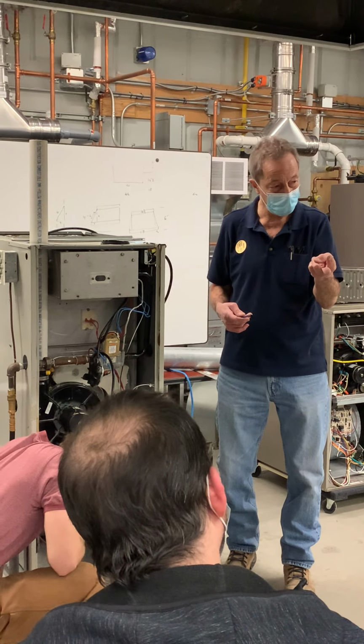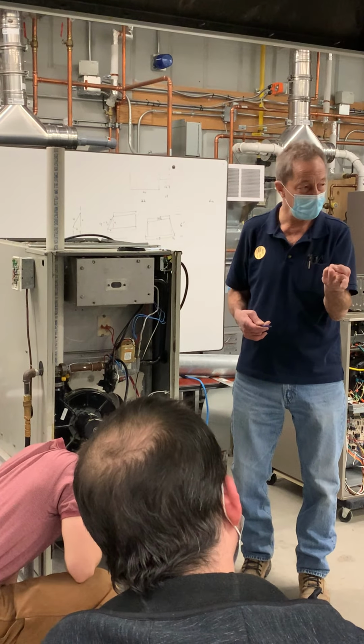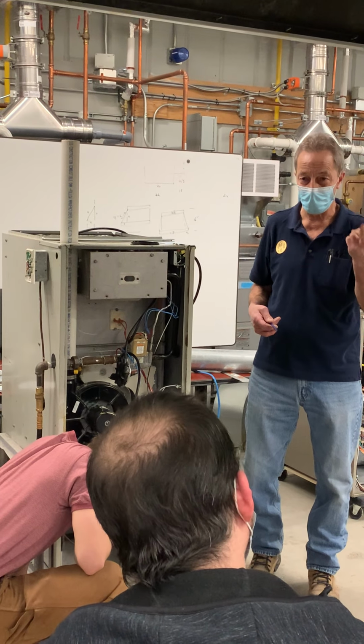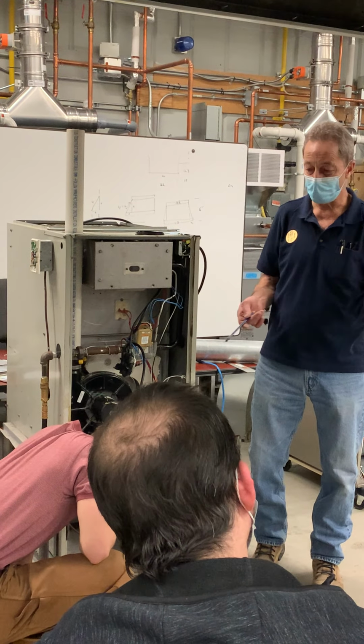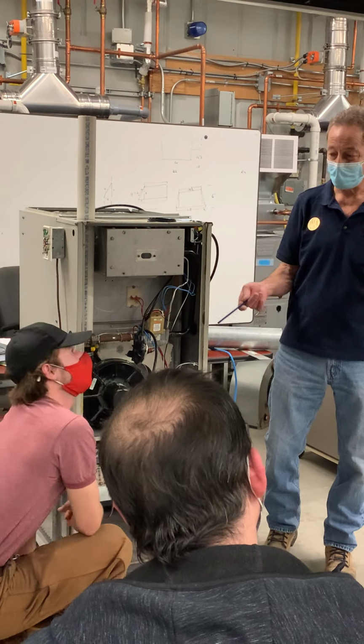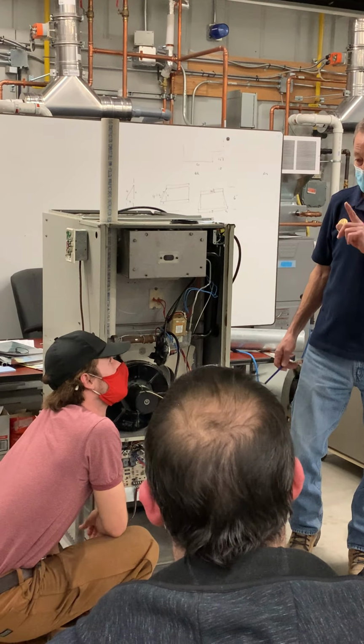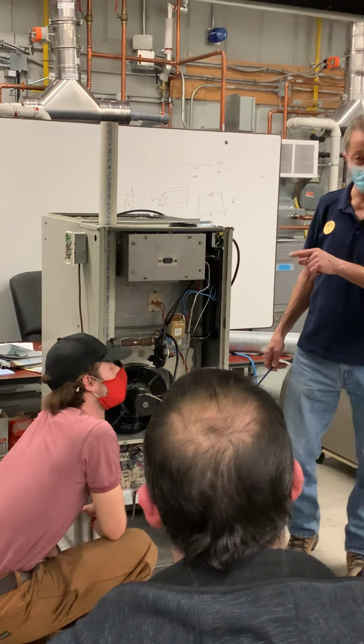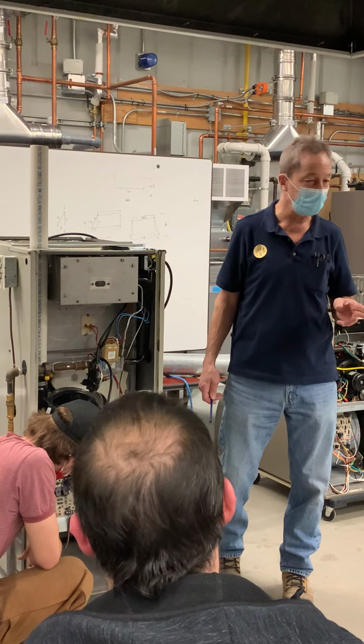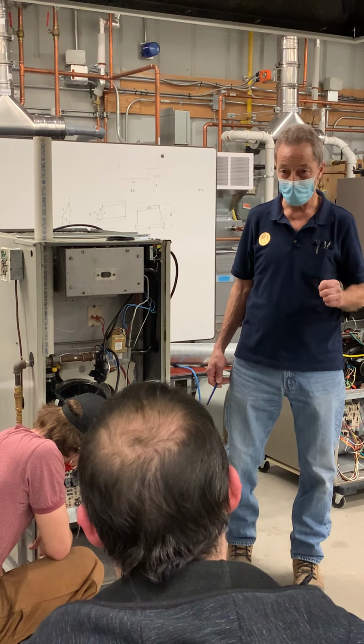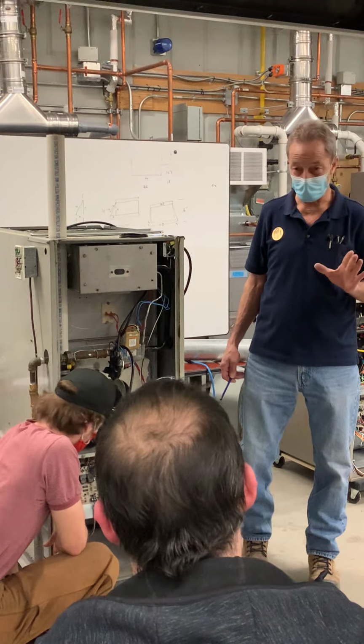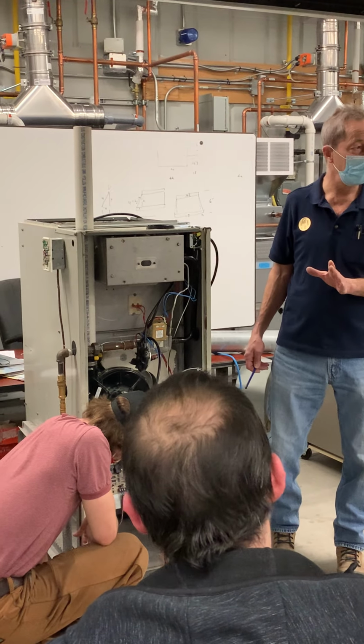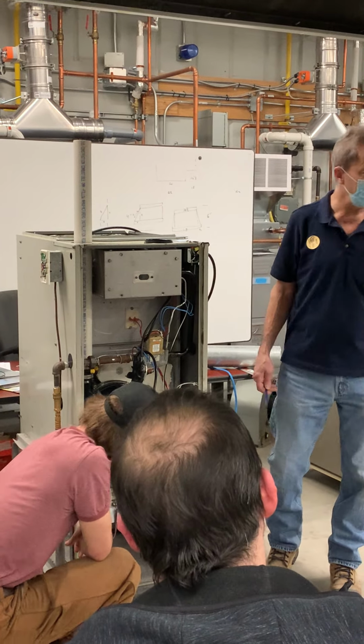Yes. Or crisscrossed, another time, and flip the other way, another time. So there are 4 fan off delays. What do you think the other dip switch is for? Fan on. Thank you. It's the fan on delay. So I can set this for 30 or 60 seconds for the fan on delay. Clear? So that is important in the sequence. So once I get that signal down there, we're good.